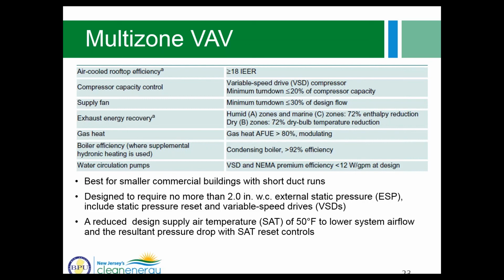Big opportunity with the systems, big opportunity for improvement is reducing energy consumed by fans, and that may be achieved by reducing external pressure, external static pressure drop in the ductwork, specifying larger size ductwork, also reducing flow rates by reducing design supply air temperature, and also specifying supply air temperature reset controls.